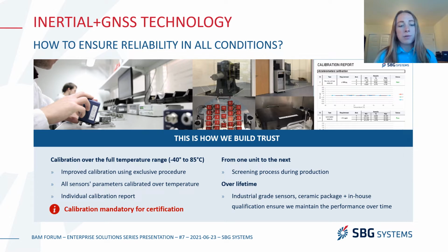These calibrations compensate for the discrepancies seen in MEMS-based sensors. For example, we calibrate all of our sensors over a large temperature range, from -40 degrees Celsius to 85 degrees Celsius, because MEMS sensors are sensitive to temperature change, especially at these extreme levels. Each sensor is delivered with a calibration report, as you can see on the top right, stating it has passed all of our tests and shall work within the given specs.